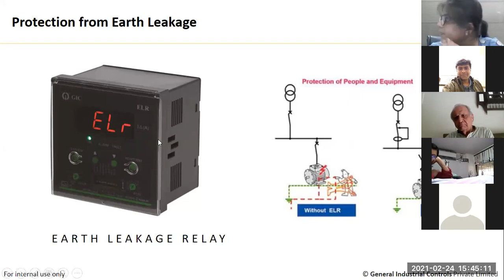If any tripping is happening, you can see on the display, it will show ELR, that's leakage current. Here we have a few features and USPs. The first is the LED display. This is a 4-digit, 7-segment display, which you can see here. The next is a wide range. It starts from 30 milliamperes to 30 ampere. Then we have 3 LEDs. One is for power, the second is for pre-alarm, and the last is for fault.